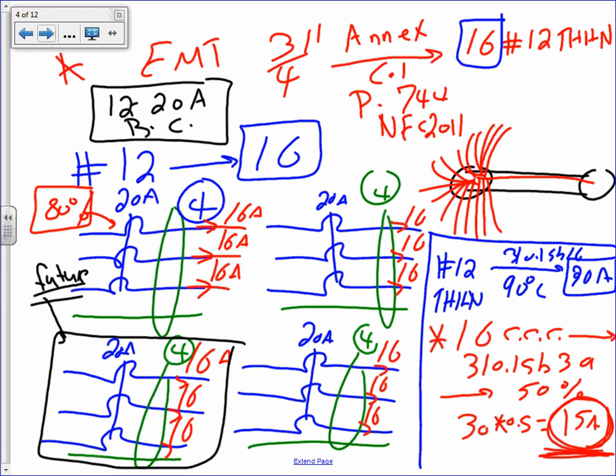Here's what I suggest. Here's your conduit, 3/4 of an inch. This is my conduit, 3/4 of an inch EMT. Okay, now do the rating. Let's use the rating here. I have number 12, 310.15 B16, 90 degree, give you what? 30 amps. I'm going to do it.